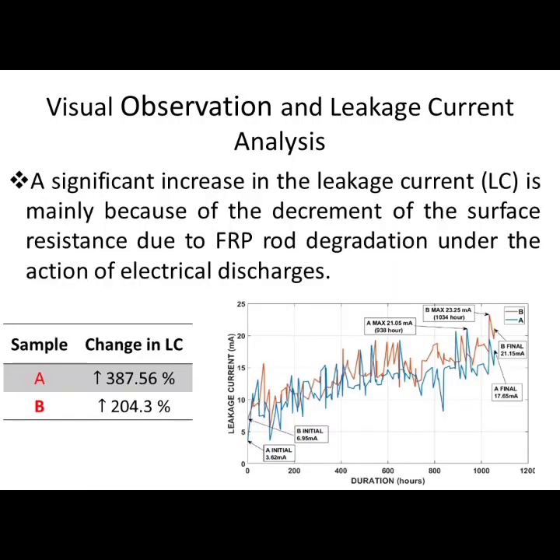This figure shows the leakage current of both samples during the experiment, where a significant increase in the leakage current is seen for both samples, which is mainly because of the decrease of the surface resistance as a result of the degradation of the FRP rod surface under the action of the electrical discharges.